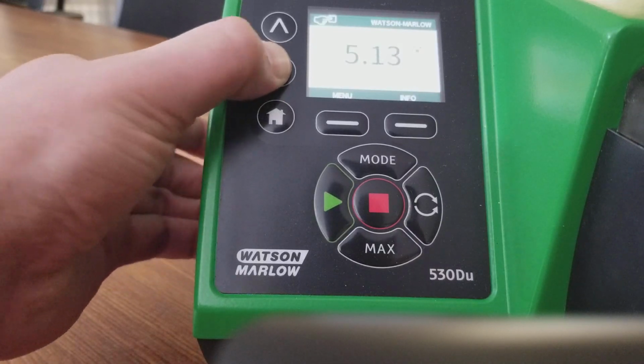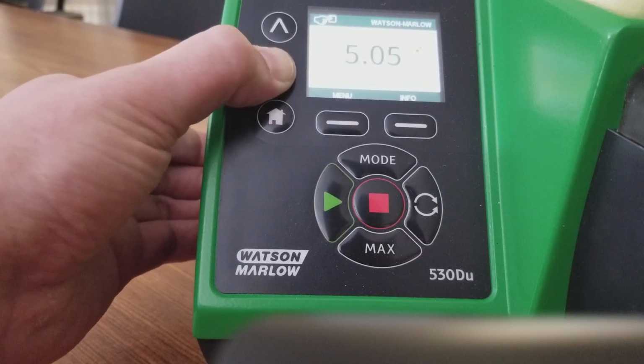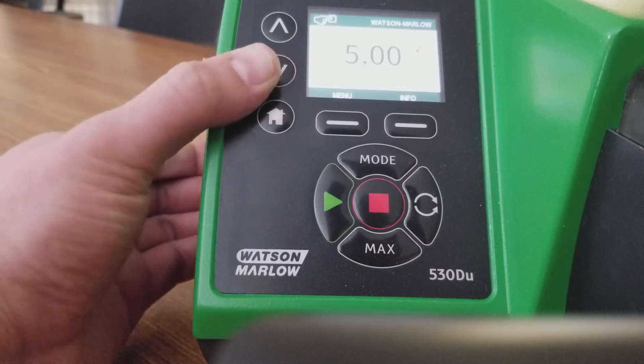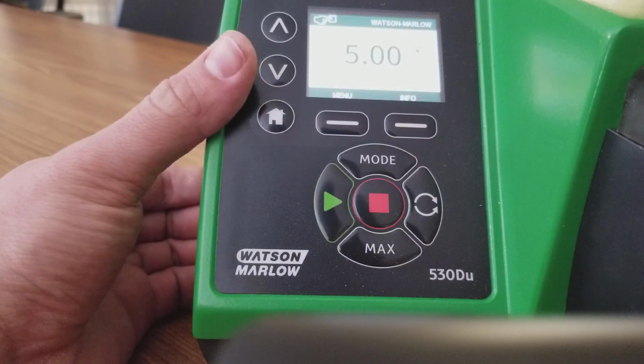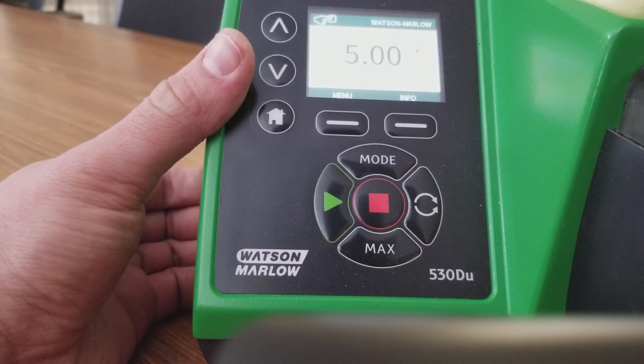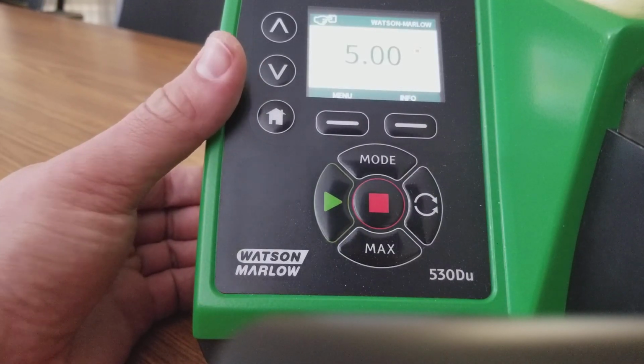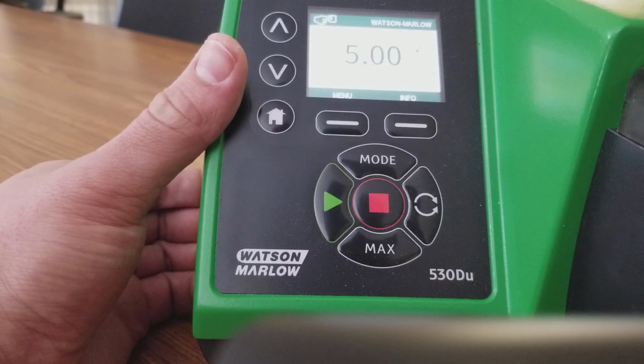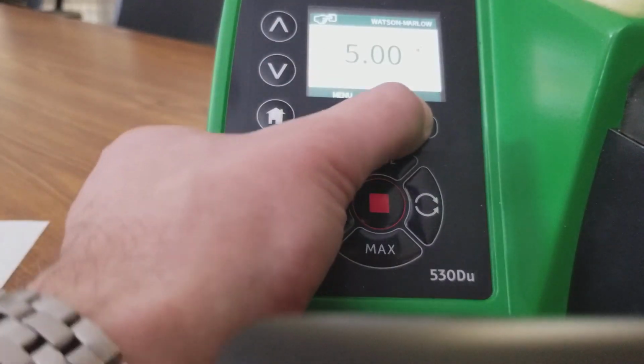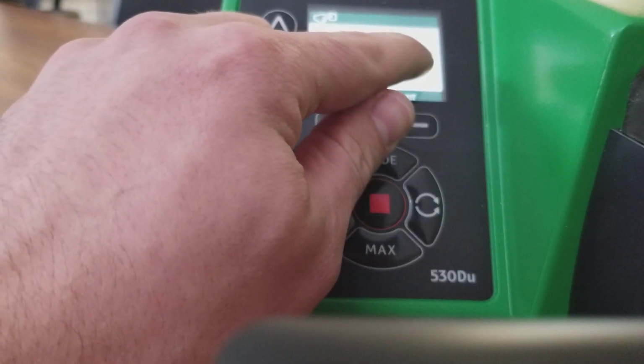This would be setting up basically the parts per million feed rate that you would figure out, and then you can set it up so that it would be linear. Let's just say that the engineer said that they wanted it to be 5 gallons per hour based upon the flow meter and everything else. At this point, if we hit the info key, you'll see that we got 187.8 RPM. At that point, we would just do the math. This pump is a 220 RPM pump, and at 5 gallons per hour was 179.2 RPM.